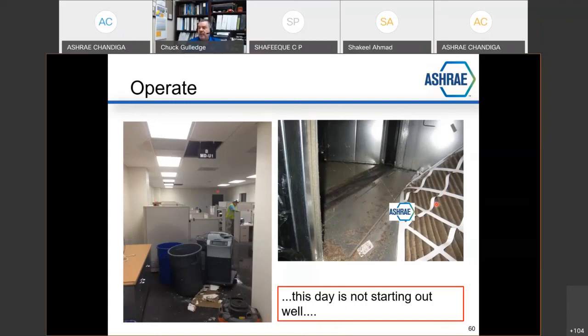There was enough static pressure between the filter and the fan that was holding all of the chilled water, the condensate off the coil in the drain pan, from all getting out. And when that filter collapsed, all of the water that was going to my right that was in that drain pan overwhelmed the drain point that it was going to, and it all flowed out into the office. That was a fun day.